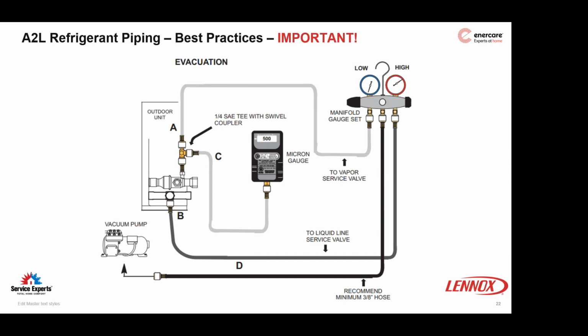Once a pressure test has proven to hold and is shown to be leak free, the system will be evacuated from both sides, low and high, as pictured, and the vacuum monitored by an approved quality micron gauge while following EnerCare's operations manual section 9 evacuation procedure. To speed up the evacuation, use your core removal tools and a 3/8 central vacuum hose from your manifold or one of those vacuum trees. They work pretty good. Remember to put the cores back in before charging, though.